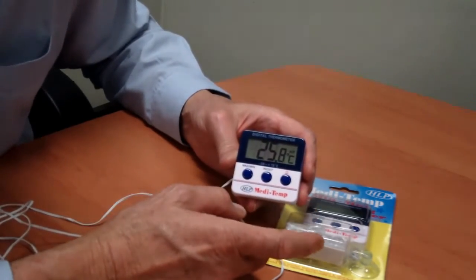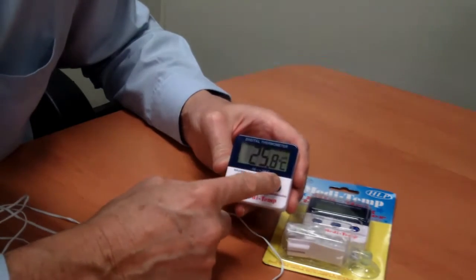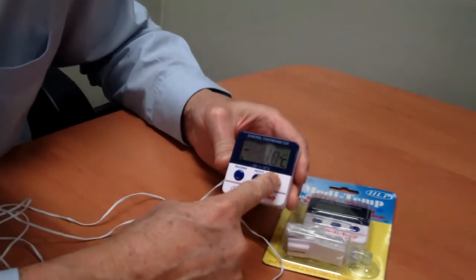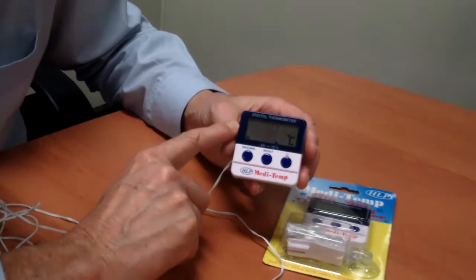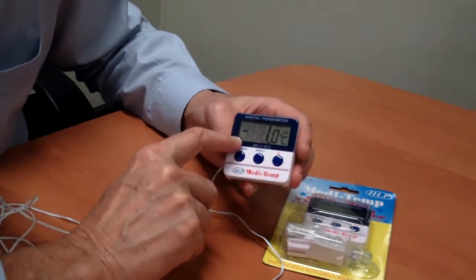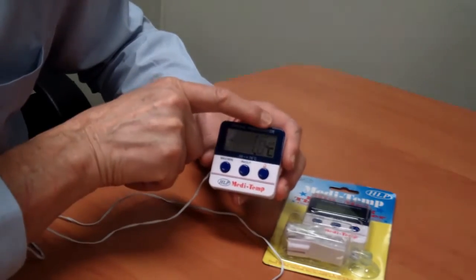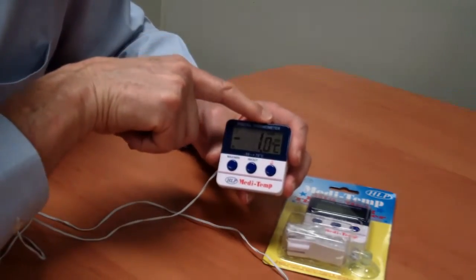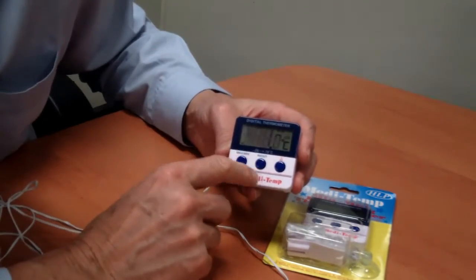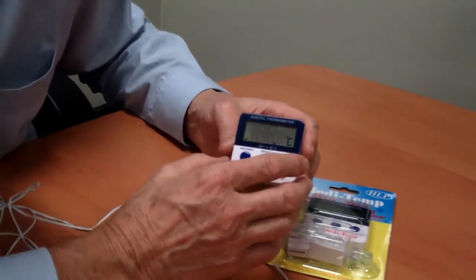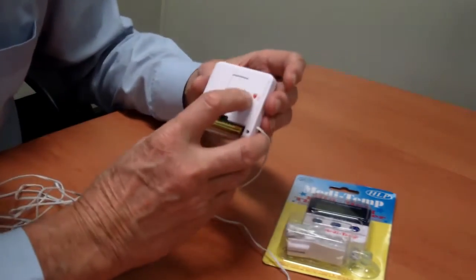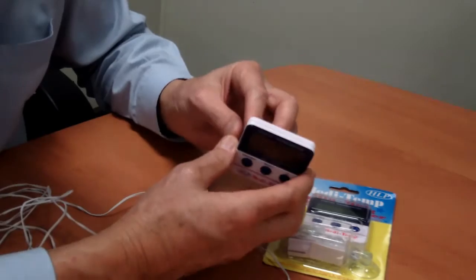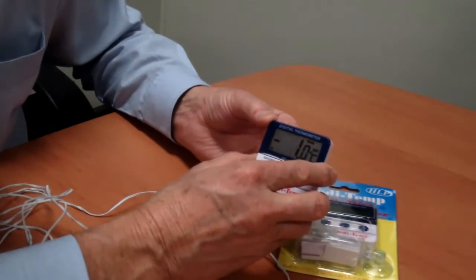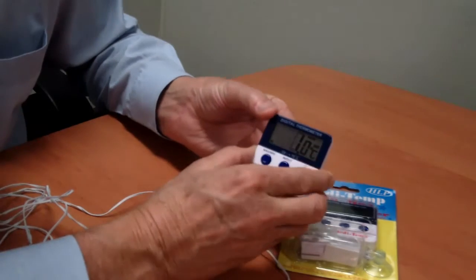So if I wanted to set the alarm, what you can do is you can push the AL button and hold it until it comes up with this display which is flashing. Now it says AL, up at top it says high, out. Obviously I want the out section. Now high, what do I want to set as the high alarm? Well, the high alarm for my vaccine fridges is going to be 8 degrees C. So on the back of the unit there's a little button with an up arrow. So you push that little button and the display will increase.